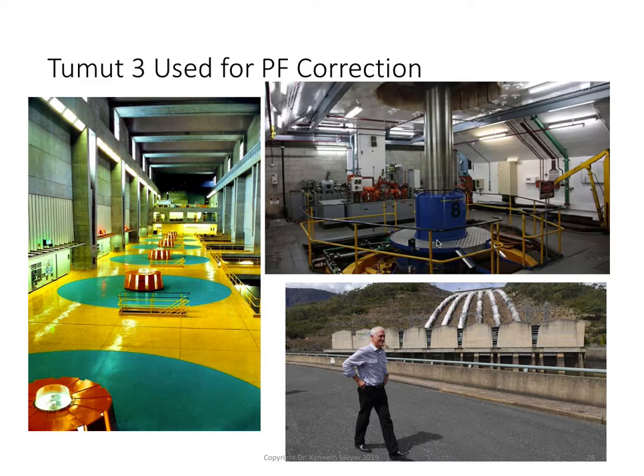So the big generators at Tumut 3 Power Station, you can see our ex-Prime Minister here walking past the power station itself. It's at Talbingo, is Tumut 3, and those three generators there can operate as synchronous motors. We can over-excite them and cause them to create VARs, and those VARs can then be added to the New South Wales electrical network to do power factor and voltage control. So not only can we add just straight capacitors, we can also add these synchronous machines as rotating capacitors to do a similar thing.